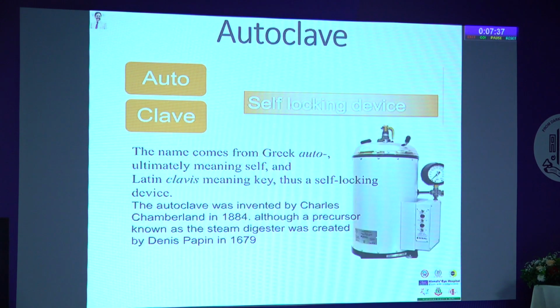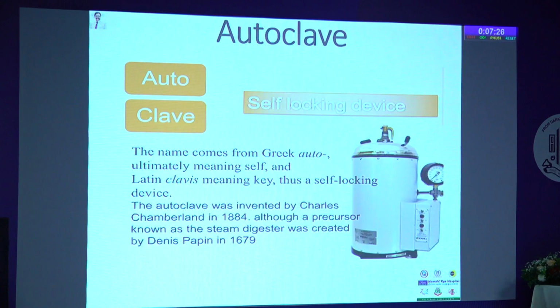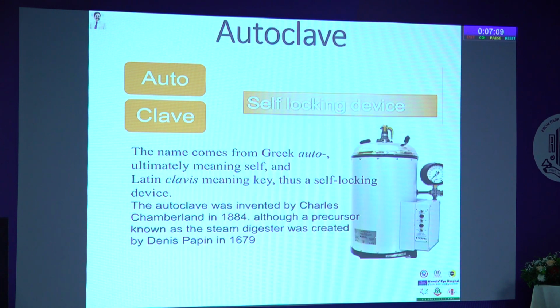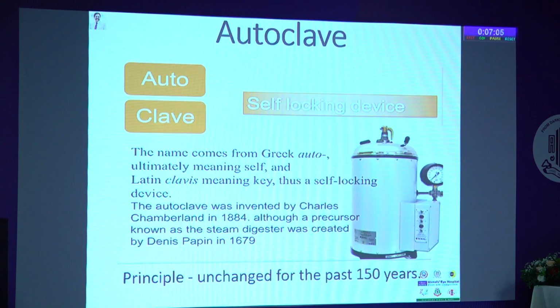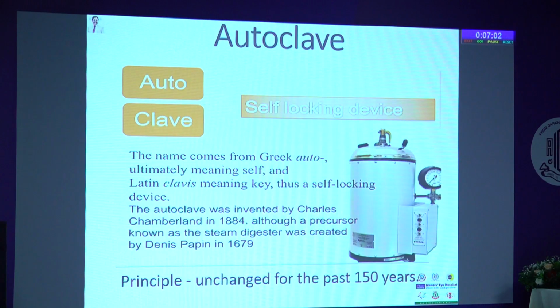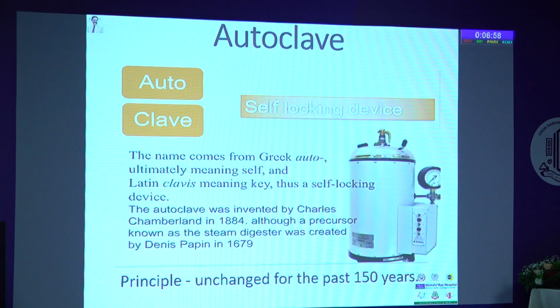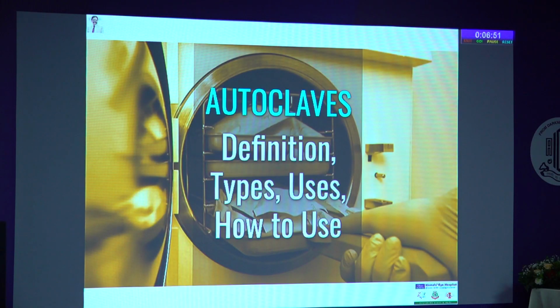As the name indicates, auto means it's a self-locking device. Clave means lock. So what happens when we lock the instruments or our bundle is the major focus. It's a Greek name, and Latin means key. So it's a self-locking device. It was invented in 1884, and we are talking about this same principle and same device in various sizes and a few additions even after 150 years. So it has stood the test of time. The principle is unchanged for the past 150 years. Most people know the basic principle is similar to that of a pressure cooker that we use in our houses. My talk will be focused mostly on the definition, the types, and how to use.